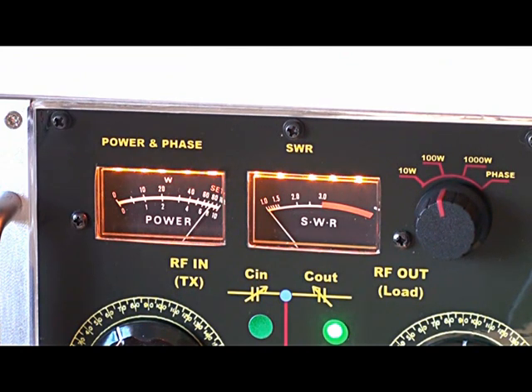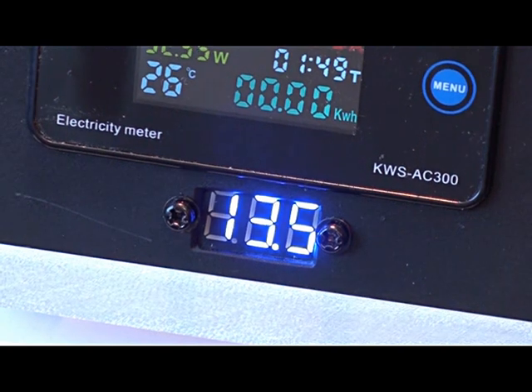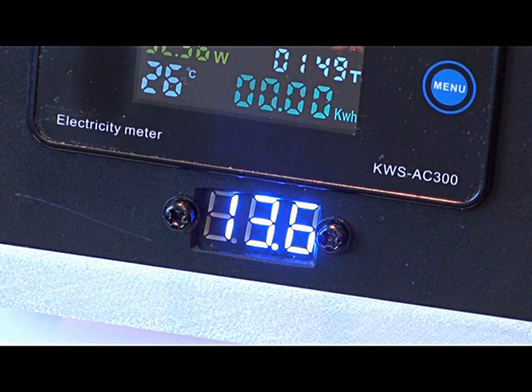The power supply doesn't have any trouble with that. The voltage has fallen from 13.6 to 13.5. So there it is at 13.6 with no transmission, and 13.5 under load, so it drops 100 millivolts with a 20 amp load on it.